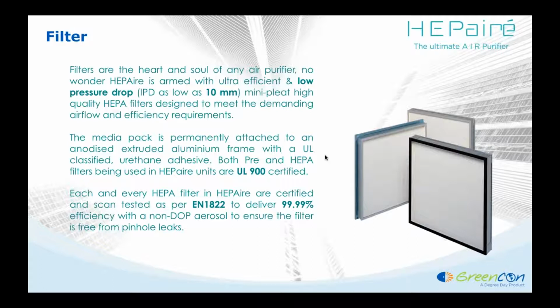I've had a case where we have been designing laminar airflows for operation theaters. My oldest installation, even after 10 years, did not require the HEPA filter to be replaced, and they were getting a perfect bacterial CFU count within the limits in that space, in spite of it not being changed.